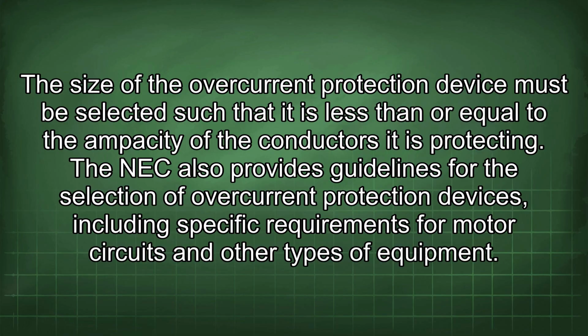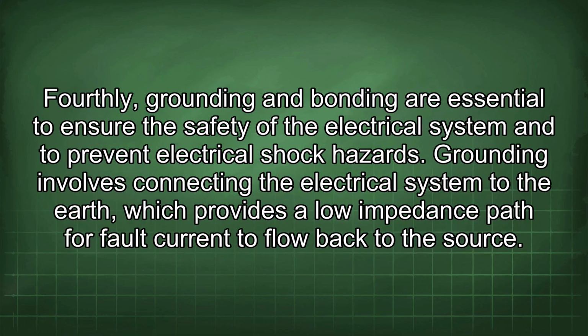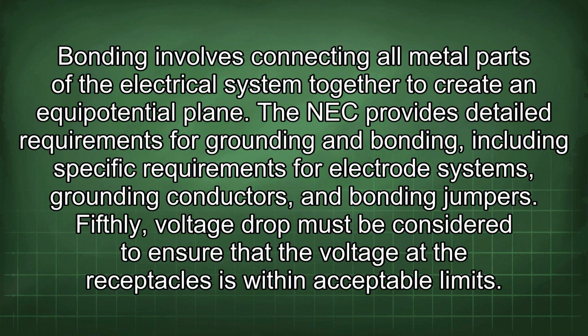Fourthly, grounding and bonding are essential to ensure the safety of the electrical system and to prevent electrical shock hazards. Grounding involves connecting the electrical system to the earth, which provides a low impedance path for fault current to flow back to the source. Bonding involves connecting all metal parts of the electrical system together to create an equipotential plane. The NEC provides detailed requirements for grounding and bonding, including specific requirements for electrode systems, grounding conductors, and bonding jumpers.